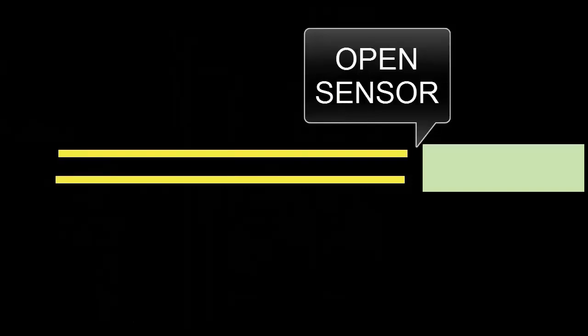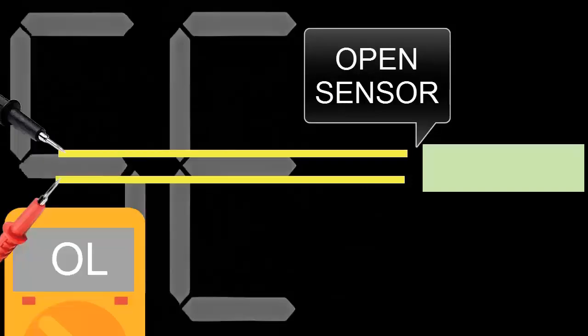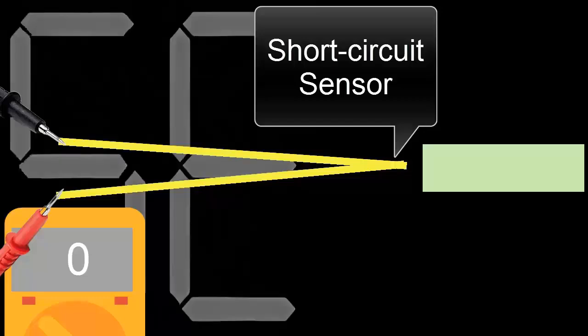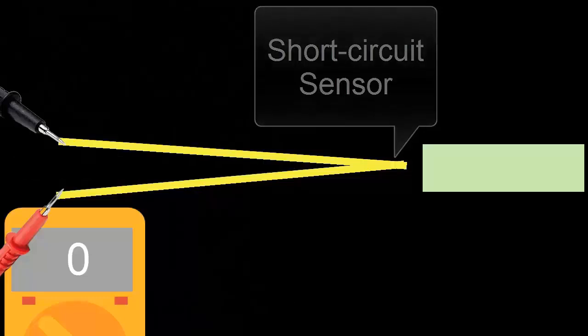Causes of the 5E error code. This error typically occurs when the defrost sensor exhibits one of the following issues. 1. Open circuit in the defrost sensor. An open circuit indicates infinite electrical resistance, which disrupts the sensor's operation.